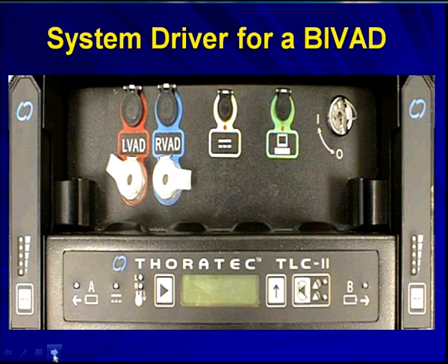Remember I talked about the BiVAD, where the patients can have left-sided and right-sided ventricular support? We may not be seeing a ton of those people in the community as much as we see the LVADs, but they do exist. And this is actually a frontal view of the Thoratec system driver for a BiVAD. If I were to take a frontal picture, it would actually look like a little carry-on bag on a set of wheels. But this is the panel which you would look at if you had to troubleshoot a BiVAD.